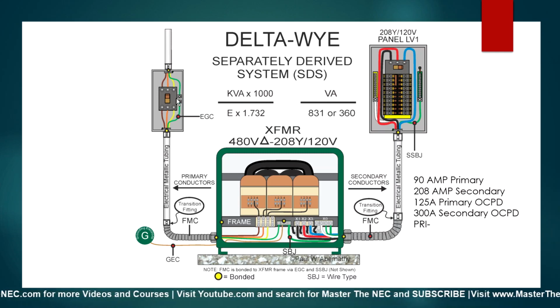All right, so primary side, we sized this at 125%, if you watched our previous videos. It was 90 amperes that we calculated as the primary current rating. At 125%, that was 112.5. It didn't correspond to a breaker size, so we went to the next largest size, which is 125. We were able to do that.